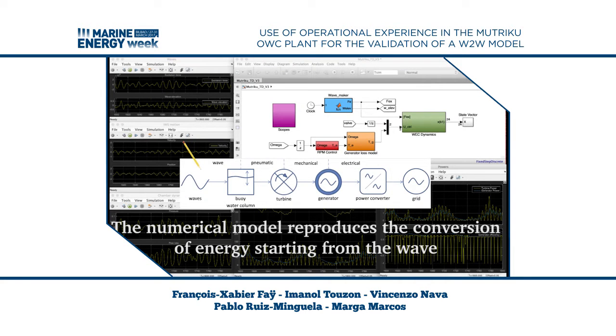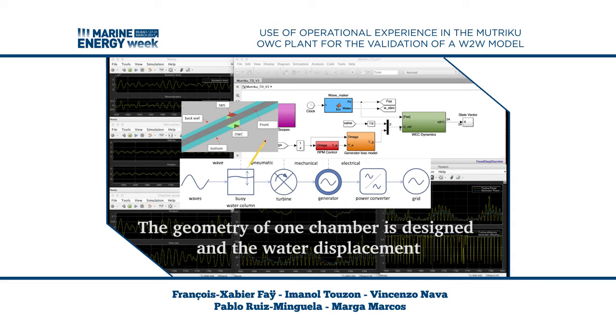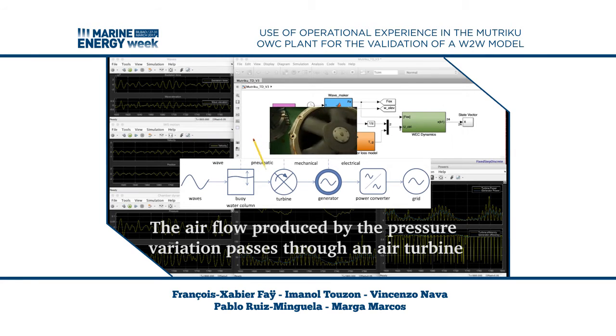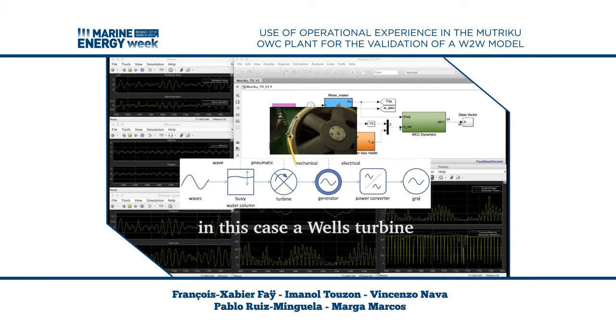The numerical model reproduces the conversion of energy starting from the wave acting on the internal water surface until the power produced by the generator. The geometry of one chamber is designed and the water displacement inside the chamber is computed using a hydrodynamic solver. The airflow produced by the pressure variation passes through an air turbine — in this case a Wells turbine — and drives the generator to produce the electrical power to be injected into the grid.